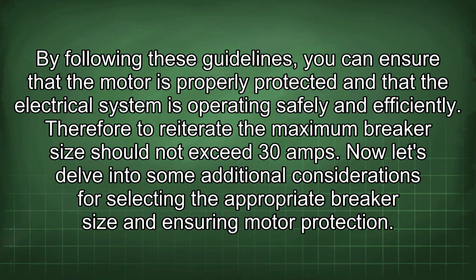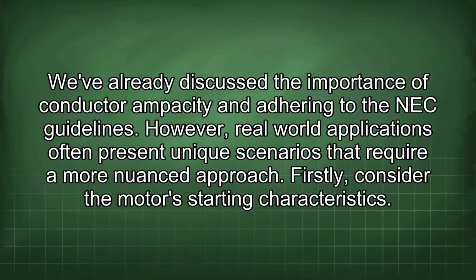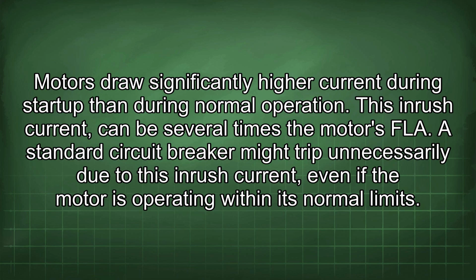Now let's delve into some additional considerations for selecting the appropriate breaker size and ensuring motor protection. We've already discussed the importance of conductor ampacity and adhering to the NEC guidelines. However, real-world applications often present unique scenarios that require a more nuanced approach. Firstly, consider the motor's starting characteristics. Motors draw significantly higher current during startup than during normal operation. This inrush current can be several times the motor's FLA.